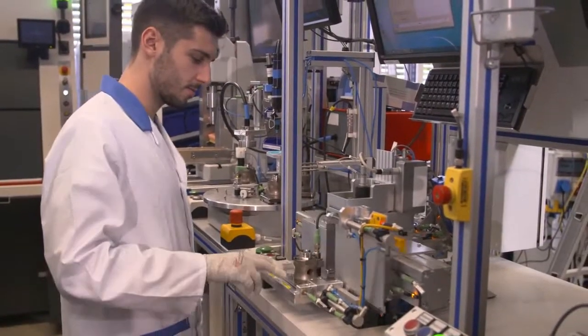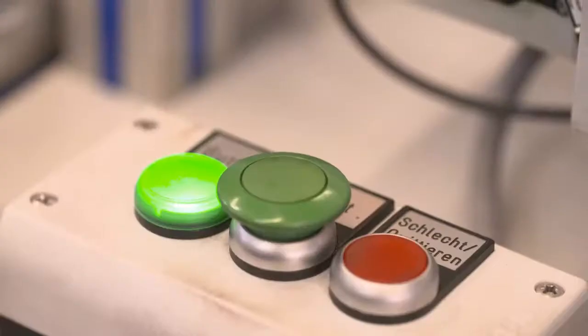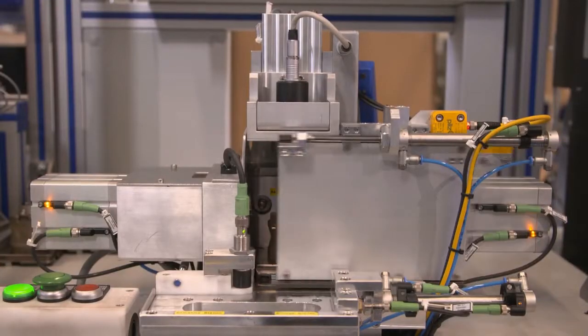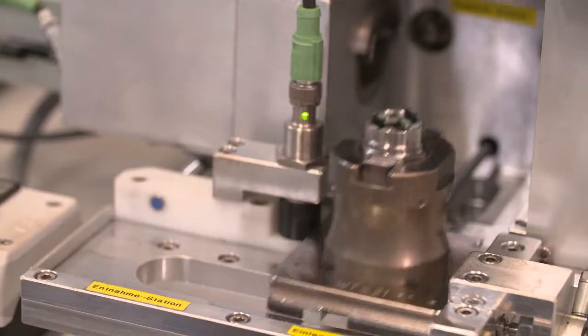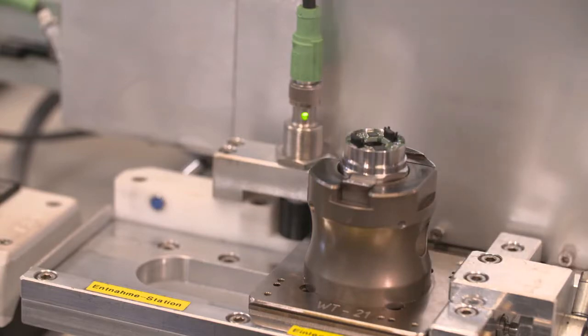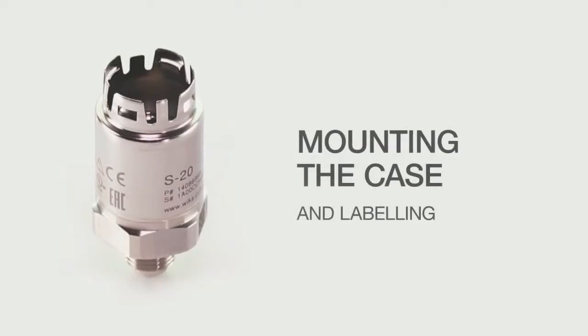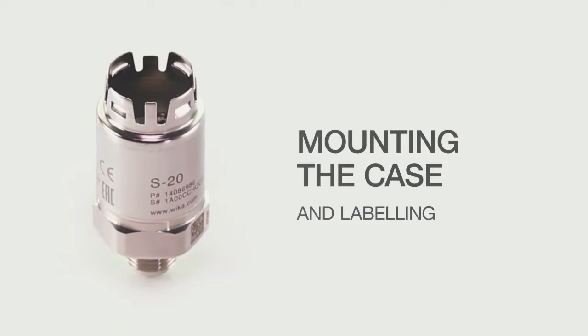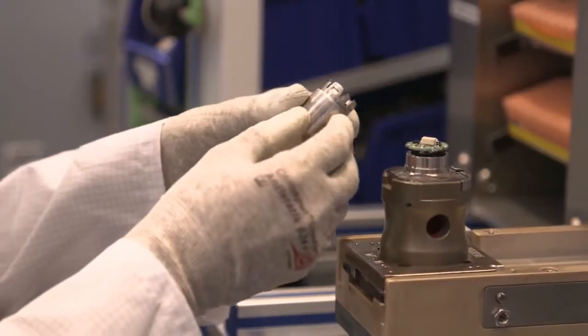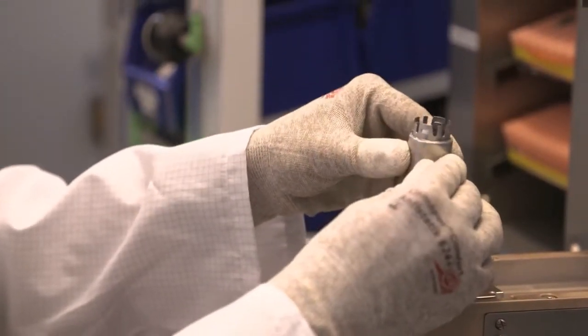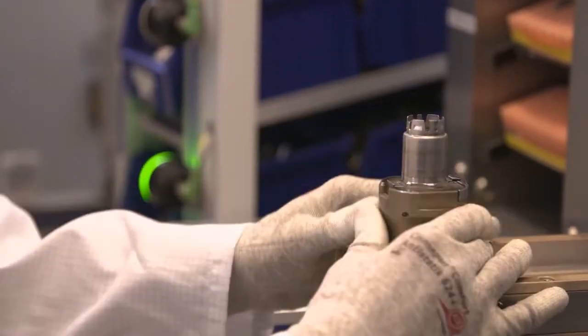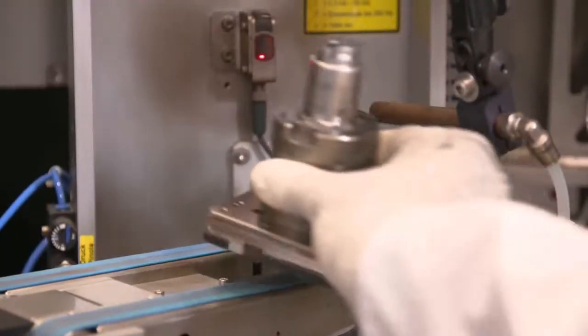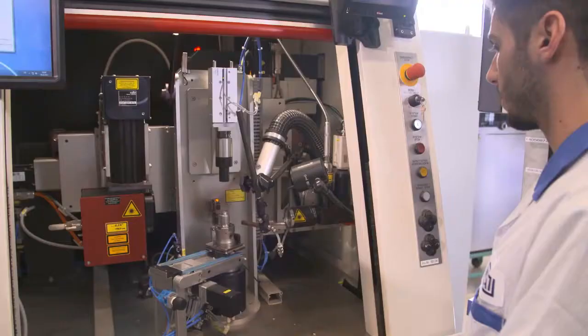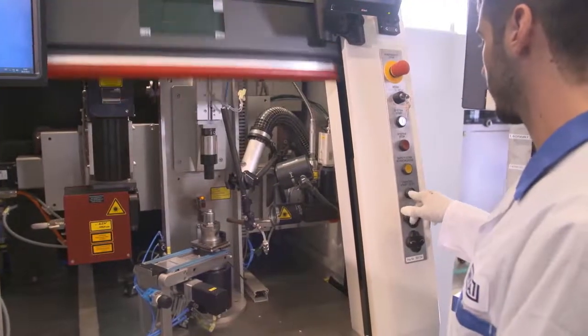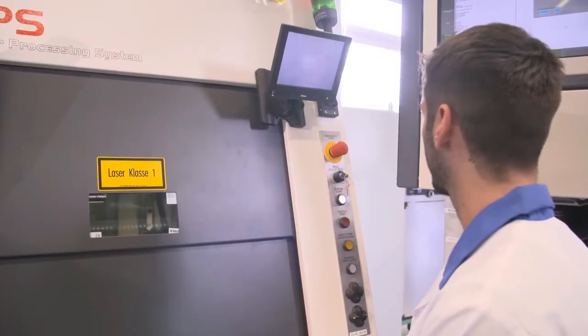The assembly is being autofrettaged. A pressure above the respective overload range is applied to the pressure sensor to ensure long-term pressure stability. In the next step, the case is mounted. It protects the electronics against mechanical and environmental influences. To improve the legibility and durability of the product label, the pressure sensors are labeled with a laser. This is done in one working step with the welding of the case.